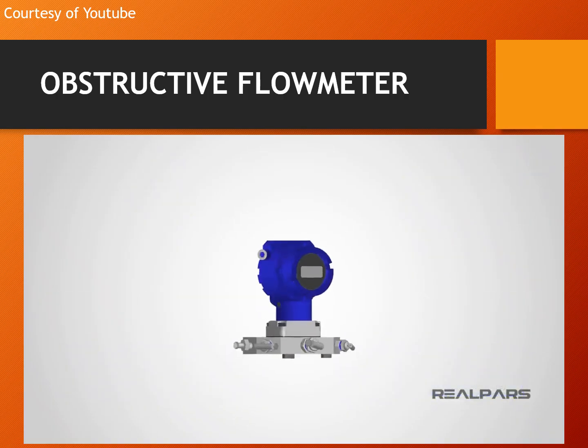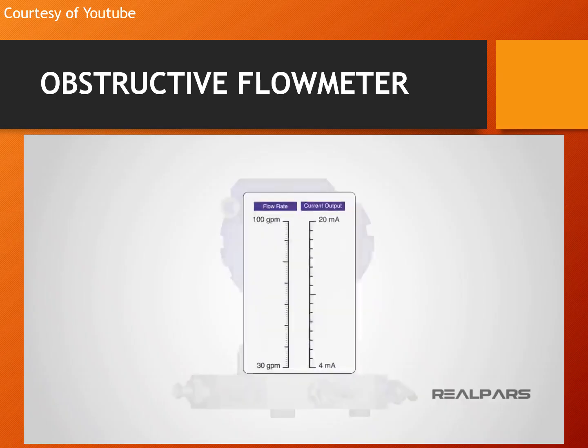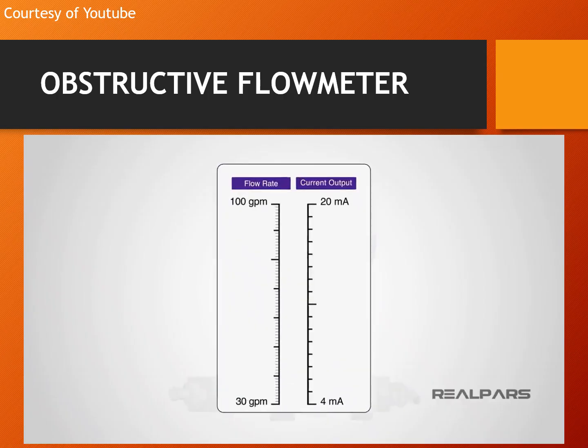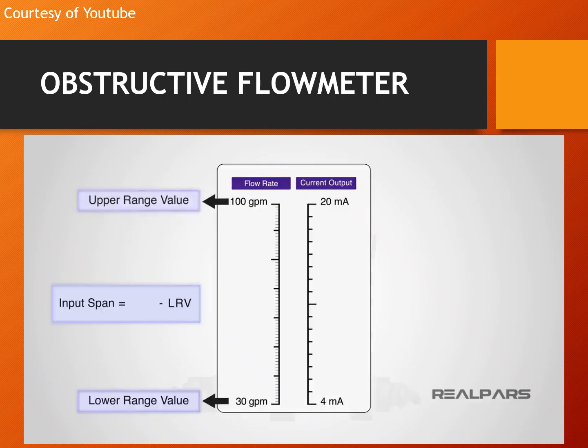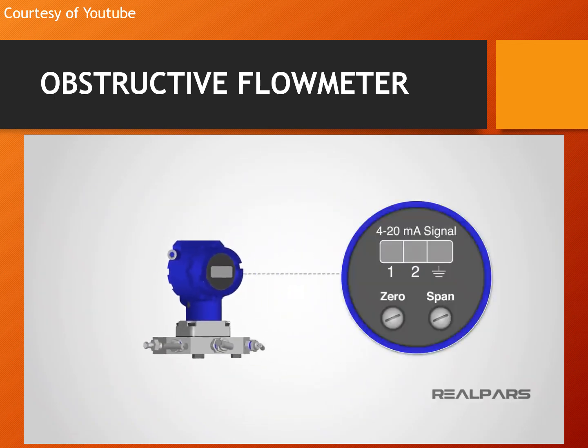Let's review what we've discussed. An instrument is calibrated when its output corresponds to a specific input across a specific range of inputs. The input span of an instrument is simply its lower range value subtracted from its upper range value. Zero and span are the names of the adjustments made in order to calibrate an instrument.